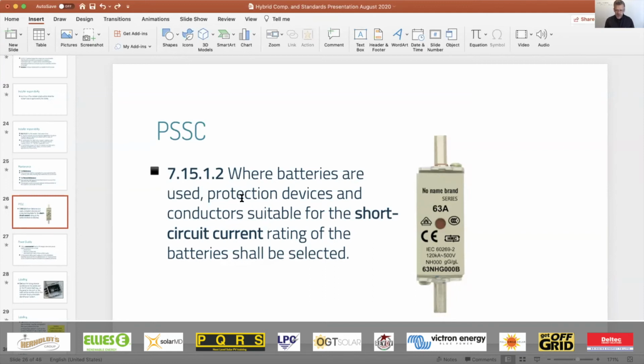What's interesting here is where batteries are used, protection devices and conductors should be suitable for the short circuit current rating. Fascinating stuff. So you've got to make sure that your conductors can not only handle the current rating, but are designed by you to be able to handle the fault current rating. Guys, there's a reason why we pay engineers to assist with designs, and this would typically be where you would get an engineer involved.